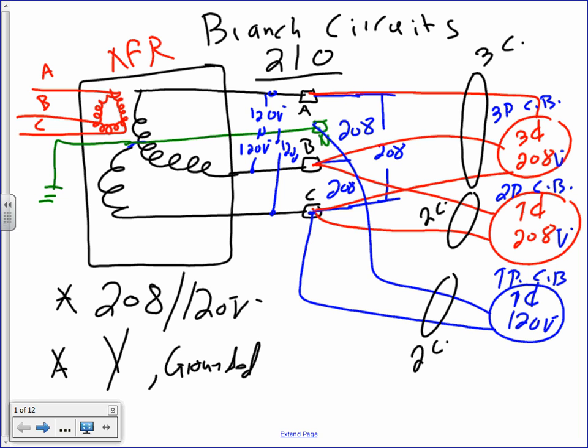Cool? Then, right in here, I threw a couple of different types of loads that you can feed from the 208/120 Y grounded. You can feed a 3-phase 208 system, no neutral. You can feed a single-phase 208 system, no neutral. And you can feed a single-phase 120 system. These are the 3 types of loads that you can feed from this system. Can you have thumbs up, Aaron, my friend, about these 3 systems that you can feed? The most confusing thing, guys, for people is they don't understand a system like this can get you 3-phase 208, can get you single-phase 208, just 2 hots, and can get you single-phase 120. Okay? Everybody's okay with that?